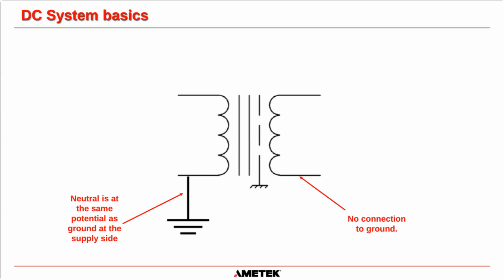But what I want to do is go through what an isolation transformer does, how it does it, and why it does it. So you can see on the left-hand side here, the neutral is usually always connected to ground, and that's from the supply side. So from your MCC or from your switchgear room, okay? The neutral will usually be connected to ground. Now, obviously, if you're coming from a delta transformer, that's maybe not the case, but this is just for illustration purposes. But what you will notice here is we have complete isolation here.